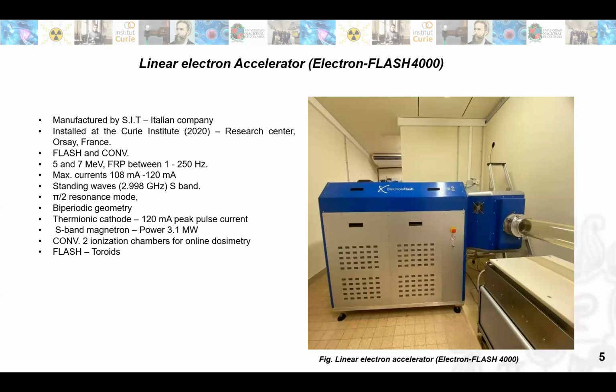The Electron Flash 4000 provides 5 MeV and 7 MeV electron beams tailored for both conventional and flash irradiation. It operates at a pulse repetition frequency between 1 and 250 Hz, delivering a peak current of 108 milliamperes for 5 MeV and 120 milliamperes for 7 MeV. It supports PMMA applicators ranging from 10 millimeters to 120 millimeters in diameter to achieve ultra-high dose rates exceeding 10 to the 6 gray per second.